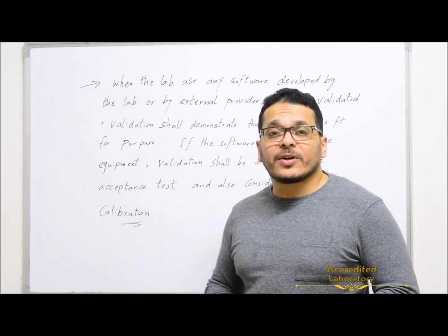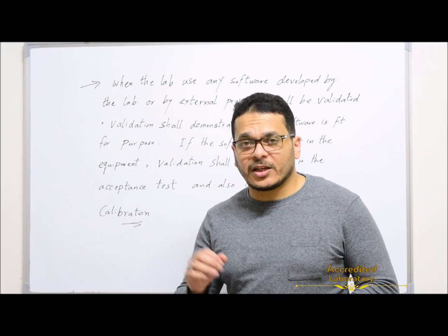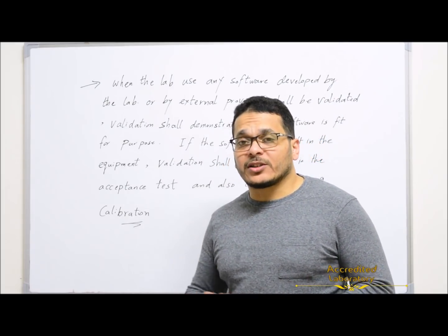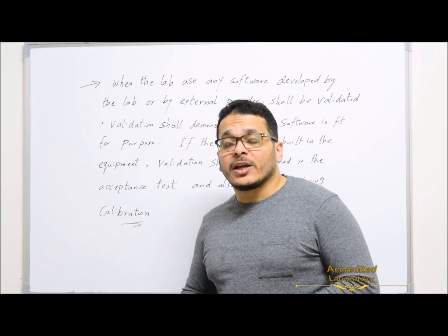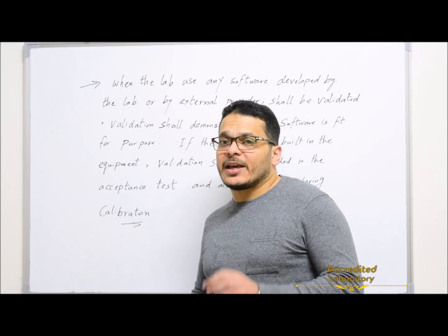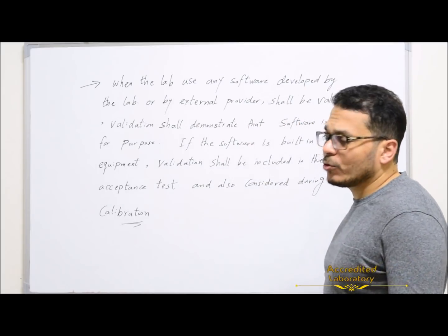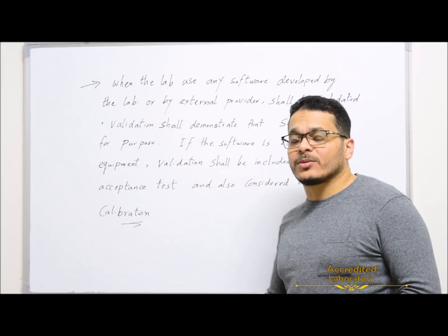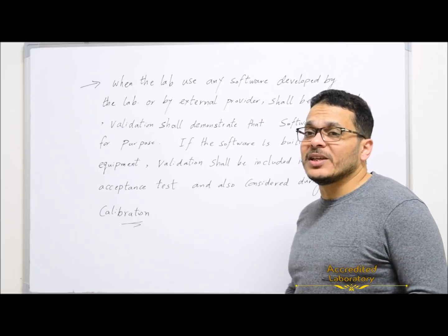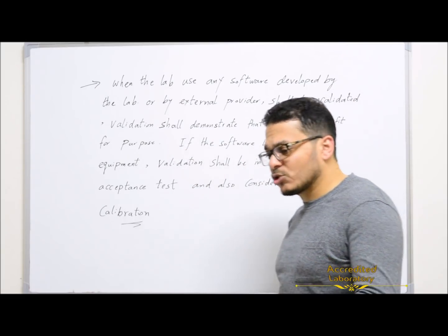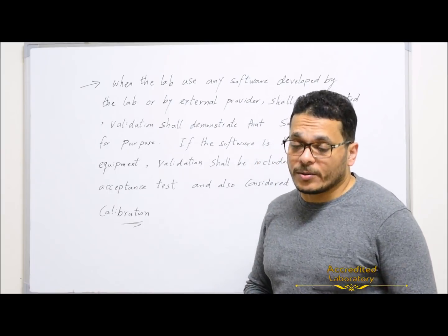And also another very important point you should take care of, which is software, because this is a new point added to this edition. Software now is considered as equipment and should be validated. When the lab uses any software developed by the lab or by an external provider, this software shall be validated. And this validation shall demonstrate that this software is fit for purpose.